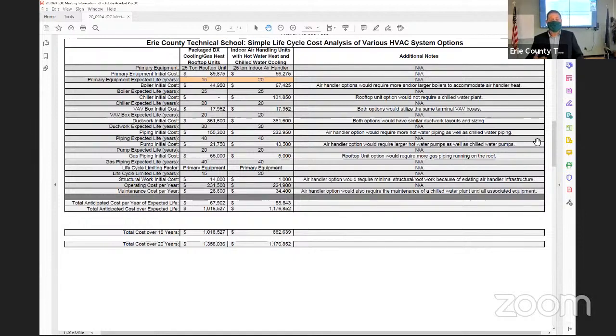However, we've seen interior air handling units go for 30+ years. Being that they're very simple units, they're inside the building, they're protected. As long as they're maintained, there's not a whole lot to go wrong with them. But for this analysis, we wanted to stay with what the industry recommendations were. So just going down through, a lot of the components of both systems are the same. Boilers, the difference with the rooftop units is we would not have a chiller. We still have VAV boxes, ductwork, some piping, gas piping.